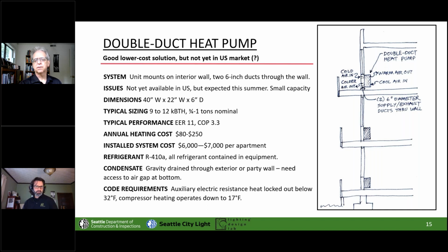Hey guys, wanted to see if we can get a tiny bit of clarification. When you guys mentioned through the wall, does that mean it is vented to the outdoors? Right. Yeah, it means the quote unquote outdoor unit that you would have for a split heat pump actually lives in the unit, similar to a package terminal heat pump, which we'll show you next. Instead of having a big old sleeve through the wall, you slide a unit in, it's just got two small ducts that do air exchange. So it pulls air in. Duane actually shows that really well. Pulls air in, takes the heat out of it, pushes that air back out again, and then uses that heat pump to warm the incoming airstream on the inside.